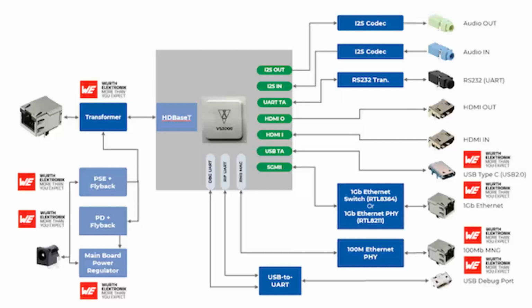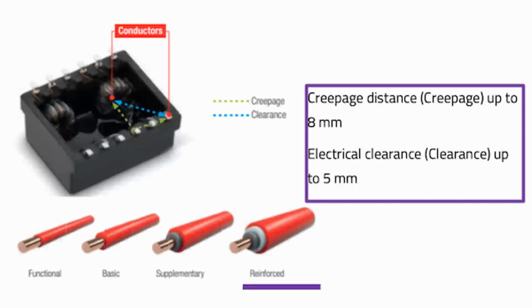To achieve a connection with a network cable that satisfies both high-speed signal output and electrical isolation between source and receiver, a signal transformer is required. Designing this transformer can be quite challenging due to the requirements of medical applications. First, to ensure long-distance signal transmission, Cat6 and above are recommended for the network cables. A withstand voltage of 4,000 VRMS per minute is required to meet IEC 60601, the technical standard for the safety and essential performance of medical electrical equipment.